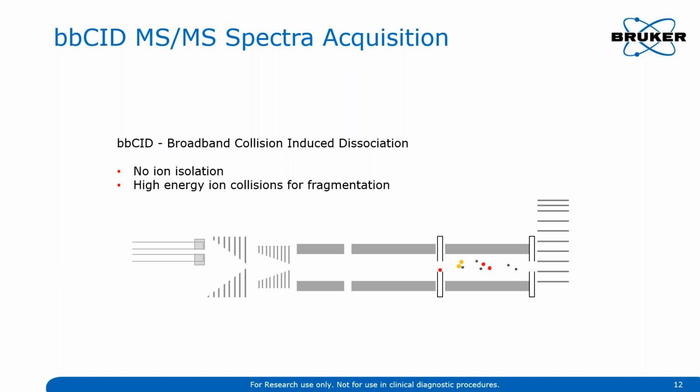Both measurements are done in a quarter of a second. It means that with frequency of 4 Hz, the system collects both full mass range parent ion scan and full broadband CID scan. It further means that it's quite enough to keep up with modern UHPLCs. Abundance of the generated fragment ions provides a rich source of so-called diagnostic ions. These diagnostic ions are used for confident identification of target analytes, and obviously, the more criteria you have to check, the more confident you can be in your identification.